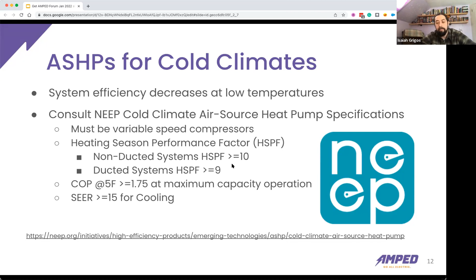So one of the ways to mitigate that is make sure you're buying the right heat pump. So there's the NEEP cold climate air source heat pump specs. They have a list online that you can scroll through and find one that suits your needs by all the different manufacturers. The things we look for: variable speed compressors, really high heating season performance factors. And then obviously they do cooling as well. So you want to make sure the unit you have operates well for cooling. Next slide.